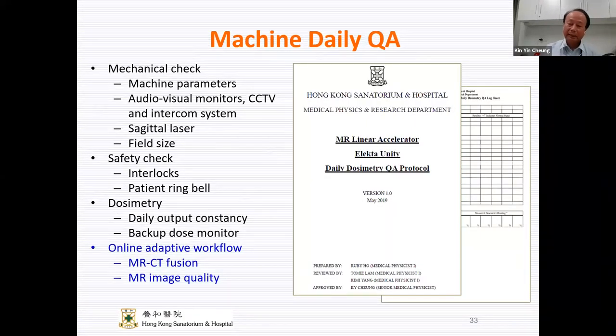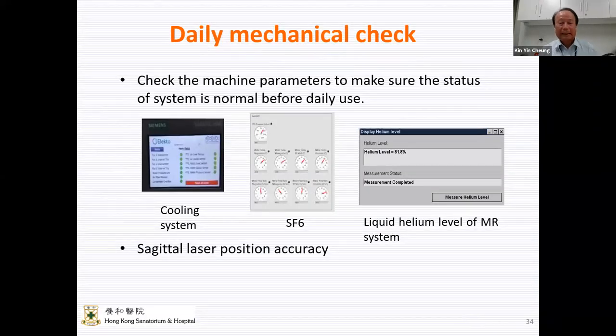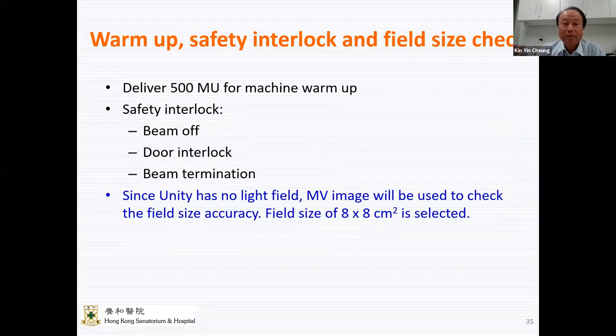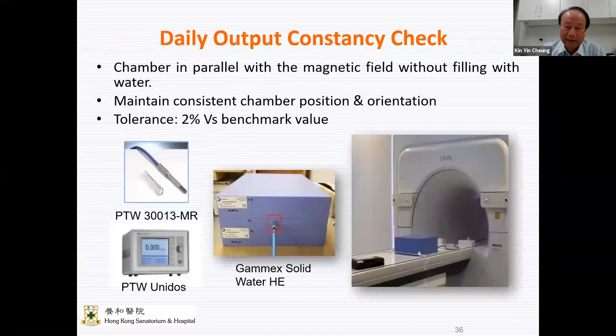And for the daily QA, I can go through a few. Some mechanical tests as recommended by the manufacturer, Elekta. So we normally check certain parameters of the machine, and also the laser, the sagittal laser system. And we warm up the machine and check the safety interlock, just like your conventional linac. There is no light field for patient setup, so we rely on the MV imager for checking the field size. So we do a field size check using the MV imager.